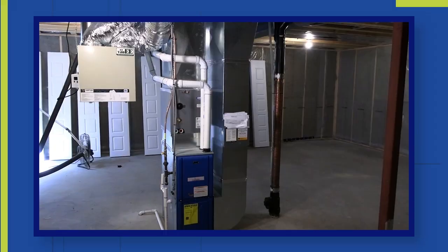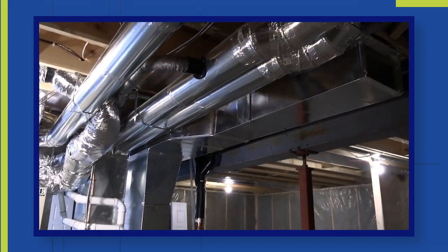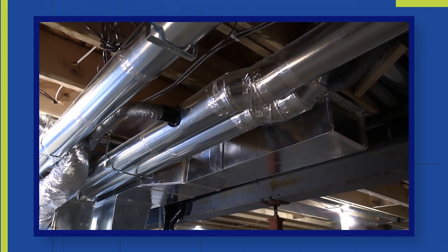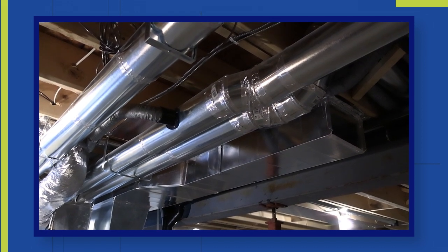There are other design elements you can incorporate in order to increase occupant comfort. One of these would be making sure that you have tight duct work that isn't leaking, and also making sure that duct work is sized properly to the loads in the home. We also take into consideration the solar heat gain coefficient on our windows, which can really help in rooms that are going to have a higher heat load.